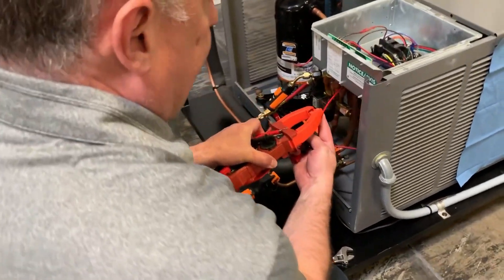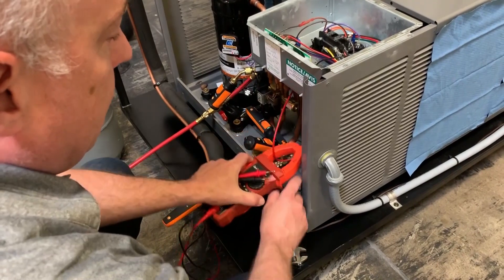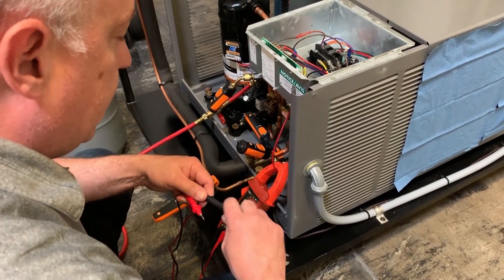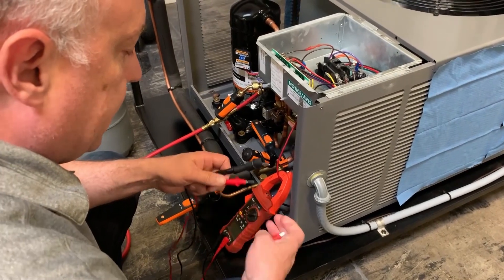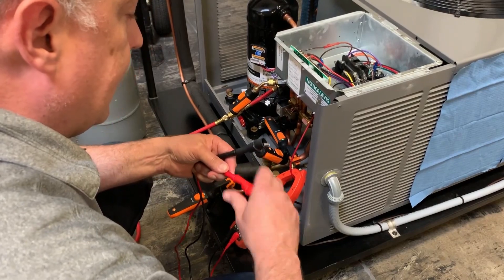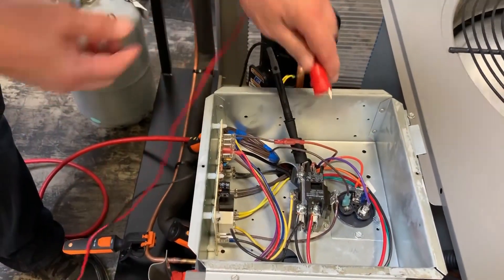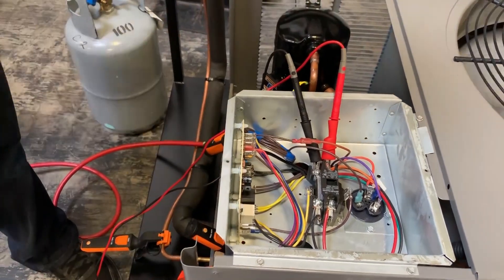Moving to the outdoor section, I'm going to clamp around the hot leg coming in off of my condenser — it can be either the black or the red leg. I'll go ahead and clamp that on to get my amps, then put the meter leads on so I can continually monitor my volts and amps in real time. I'll clip these on here — one on each side of the 240 volt, black leg and hot side.